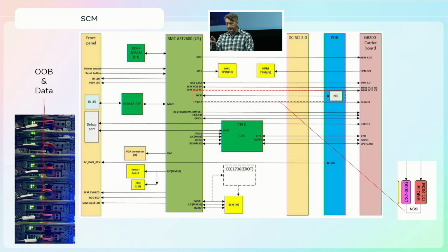If you see the LEDs on that picture on the left, where you see the different green LEDs, often if you have a leak, a failure, a power fault, some idea, you need a good first level triage of: is this something I can debug? Do I need to escalate? Do I need to bring it in? Those LEDs are meant for that.